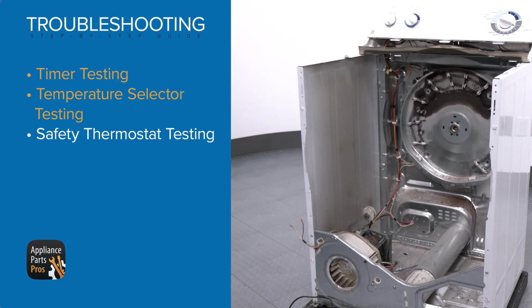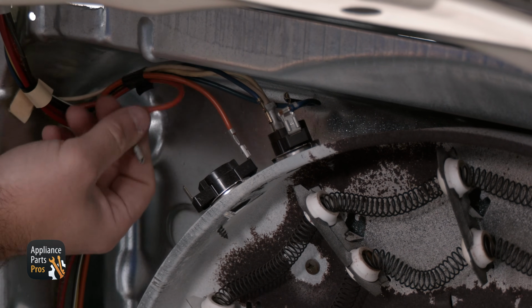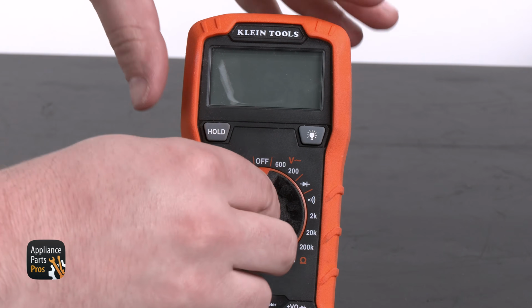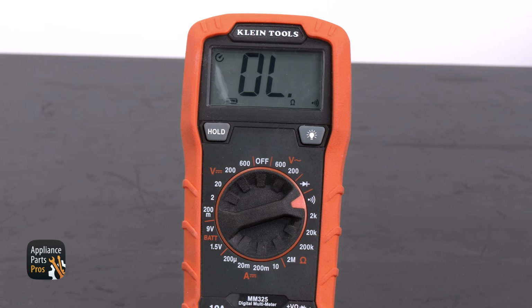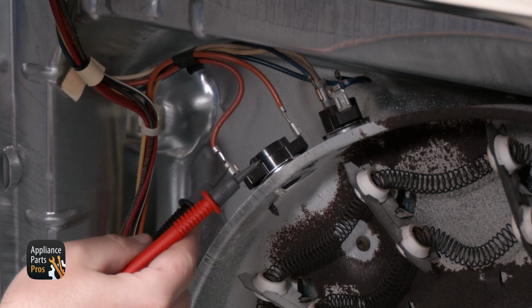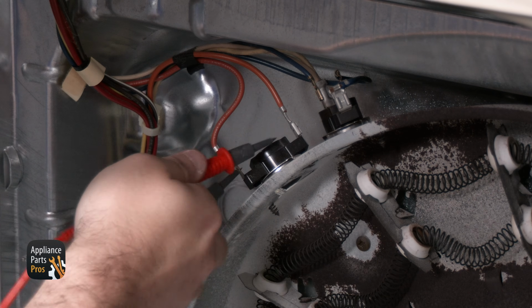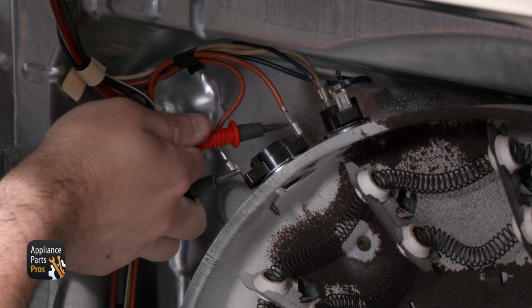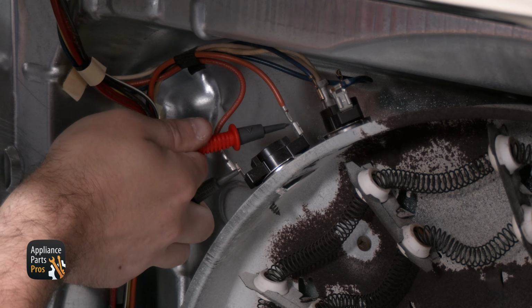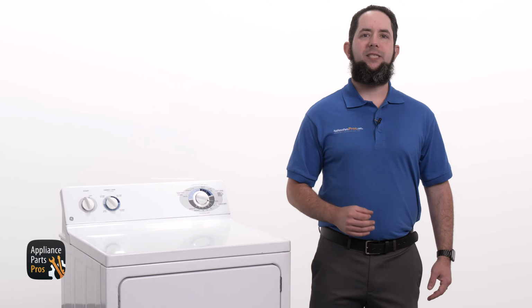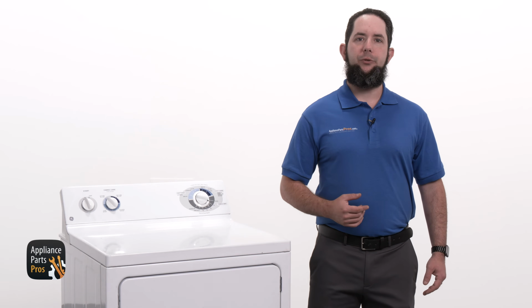With that out of the way, we can see the safety thermostat on the top of the element housing on the far left. We're going to remove one wire and set our multimeter to continuity, which looks like a sideways Wi-Fi symbol. Let's use the meter probes to test the thermostat for continuity. If there's no continuity, then the safety thermostat has failed and will need to be replaced. If there is continuity, our thermostat is good and we'll need to continue troubleshooting.